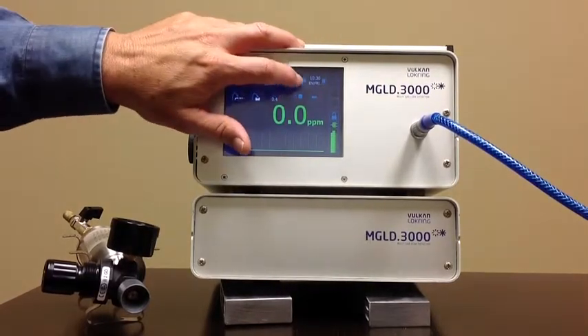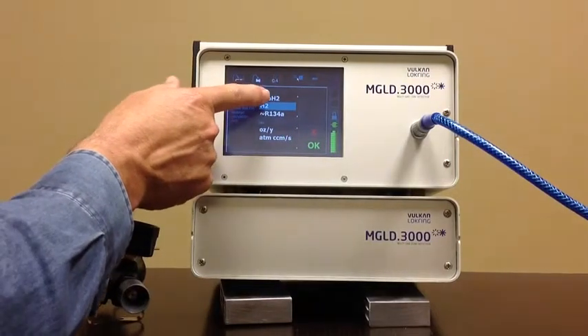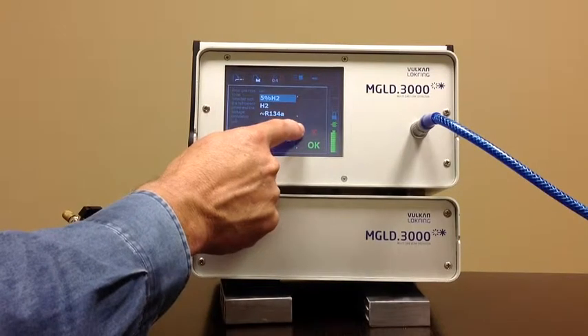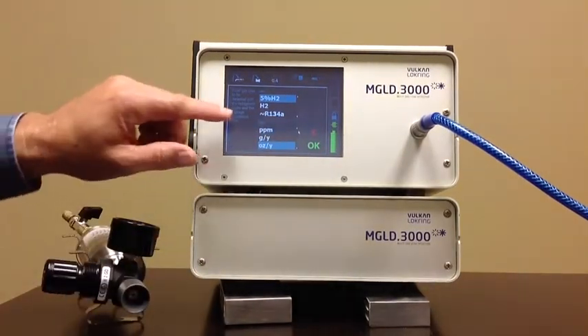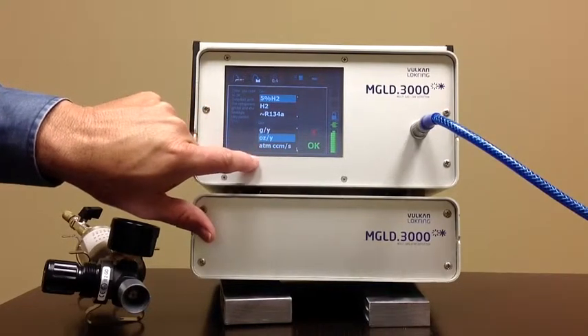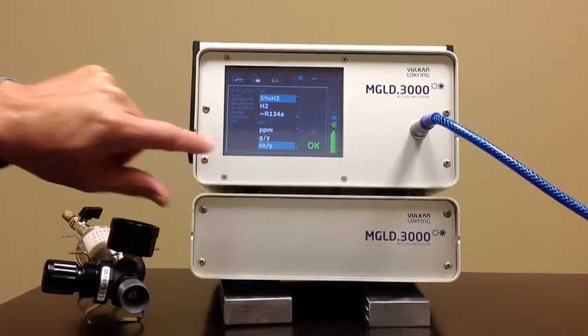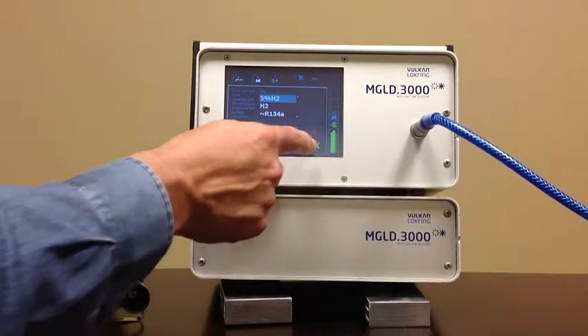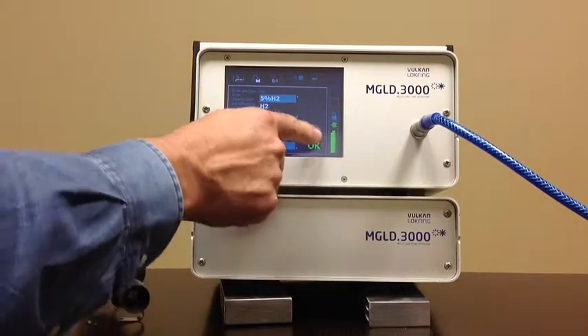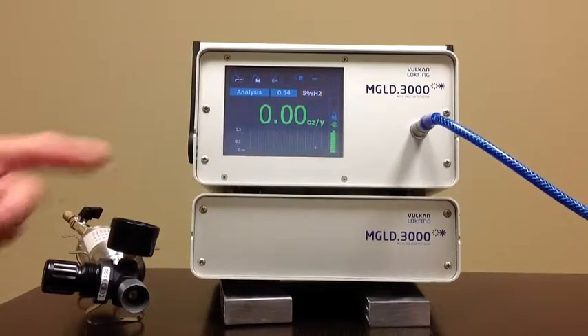Now I'm going to change the parameters as far as the gas to 5% hydrogen. You can also change the units to PPM, grams per year, ounces per year, or atmosphere cc's per second. I'm going to change it to ounces per year because that is a very common unit used in the industry. Hit OK — so now we're using 5% hydrogen and the display is ounces per year.